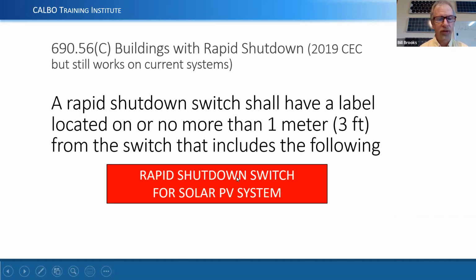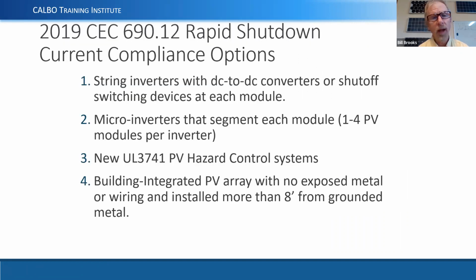All right, the switch needs to have this sign next to it. There's another sign. So what are the compliance options? We can use string inverters with DC converters or shut-off devices at each module. So that would be SolarEdge with their optimizers, or AP Systems or other types like Tigo or whatever that would have switches at the modules. Microinverters, of course, work well, and they can be for up to 4 modules per microinverter. The current products that are on the market.